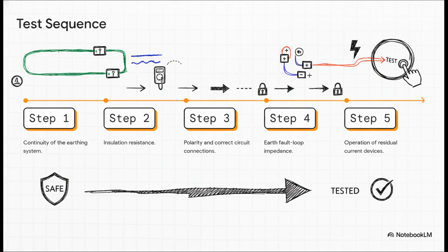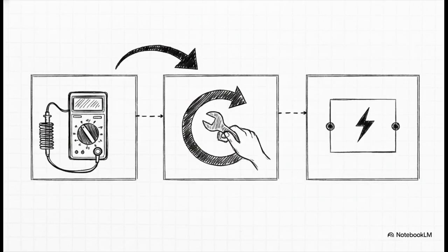operation of the RCDs. This sequence matters immensely because earlier tests actually prove the system is safe enough to perform the later tests. You literally have to prove your earth continuity before you can reliably test insulation resistance. And this chronological rule, it is incredibly rigid. Let's say you fail your earth continuity test and you have to go in and alter or repair a connection to fix it. Well, that completely invalidates any insulation tests you might have already done. Fixing an earthing issue forces you to step all the way back and re-verify the insulation. You can't just patch a problem and blindly move forward. You have to ensure that your fix didn't compromise the rest of the system.